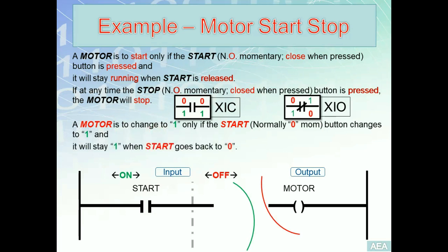The second requirement is: the motor has to stay one when start goes back to zero. Anytime you energize an output using a momentary switch and want to maintain the output on after that momentary condition goes false, you bypass the instruction used to energize the output — in this case start — with a parallel instruction that refers to the output itself (motor), using an XIC. This is the seal-in or latch circuit. A separate tutorial will cover the scan sequence concept to illustrate latching in more detail.